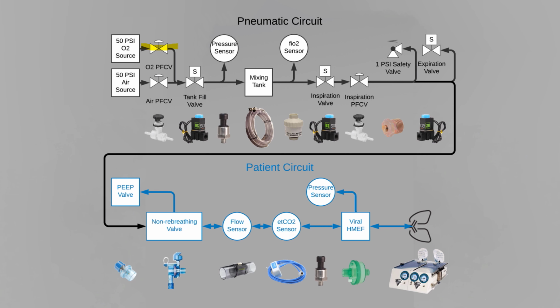So starting off on the pneumatic circuit, we have 2 PFCVs that form the blender for meeting target FiO2, and this valve fills the tank during expiration. This one releases the tank during inspiration. The last PFCV meters inspiratory flow rate, and the last valve removes dead space to atmosphere during expiration so that the non-rebreathing valve's exhaust port can open.